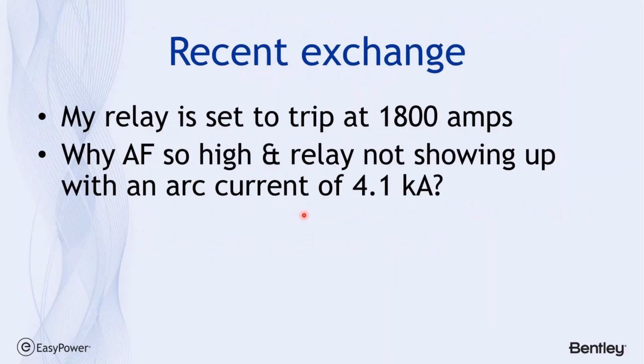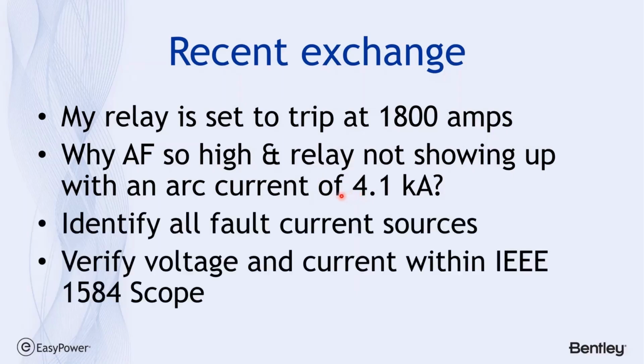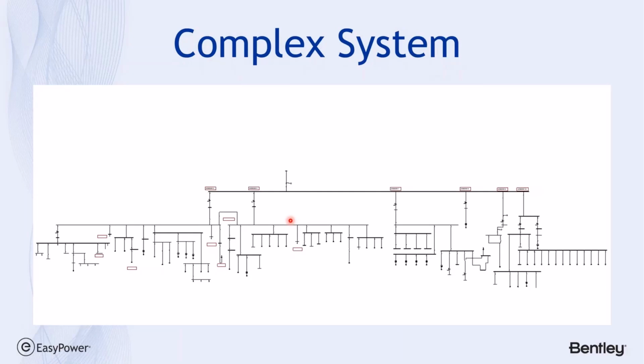So not too long ago, I had an engineer call me and say, Jim, I'm adjusting this relay and I know it's set for 1800 amps, but why is the arc flash so high when I only have a fault current of 4.1 kiloamps? Well, you want to identify the source of the fault current, and you want to make sure it's in the path of the last device that's being tripped. So let me show you what this came up as.